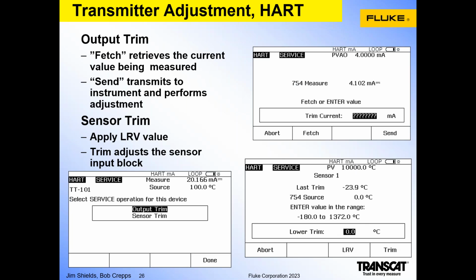On the other hand, in the instance of smart instruments, the adjustment is performed using the HART communication protocol. In this case, the HART communication protocol in the 754. In this instance, you're given the option to perform an output trim, which adjusts the 4 to 20 milliamp output signal, or the sensor trim that trims the input A to D of the transmitter to adjust the HART lower range value and the HART upper range value that are programmed into the transmitter and ensure that the digital output value that's coming out of that input A to D is accurate and correct.